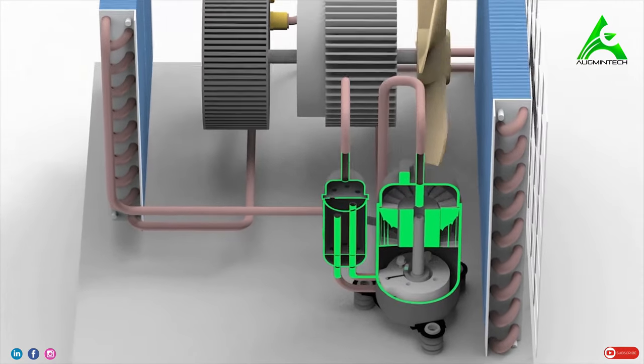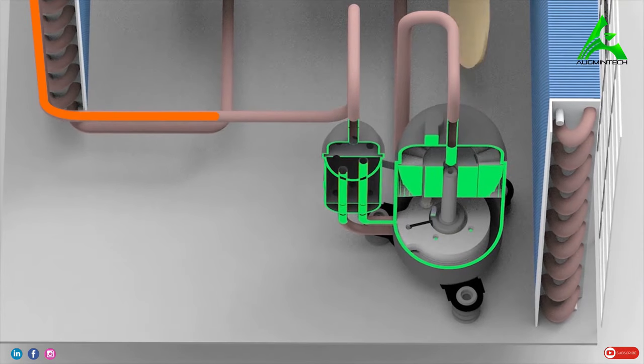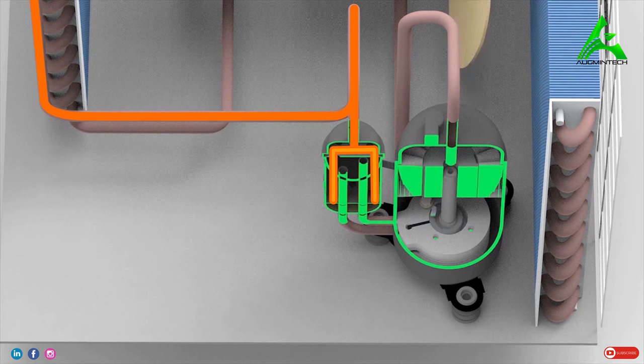Before the refrigerant enters the compressor, it passes through an accumulator. The accumulator separates any liquid in the refrigerant, thus avoiding any damage to the compressor.